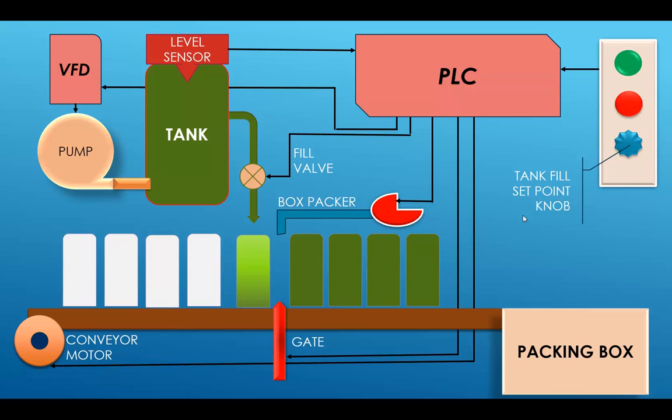Now the pump full speed is 60 Hz, half speed is 30 Hz, quarter speed will be 15 Hz, and then we drop even down to 8 Hz for the very slow speed. The higher the tank is the slower the pump will run so you don't overflow the fill process on the tank.